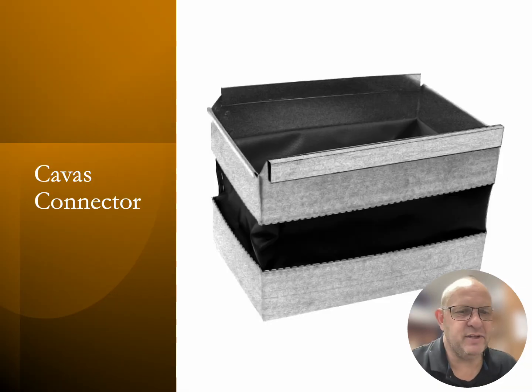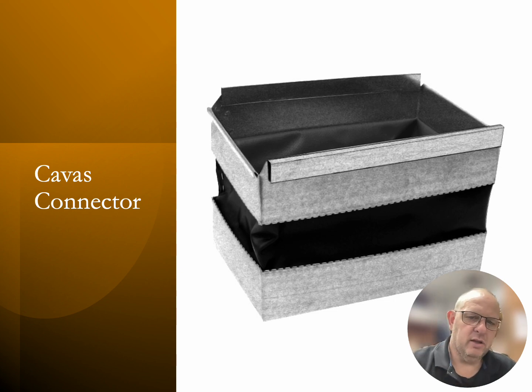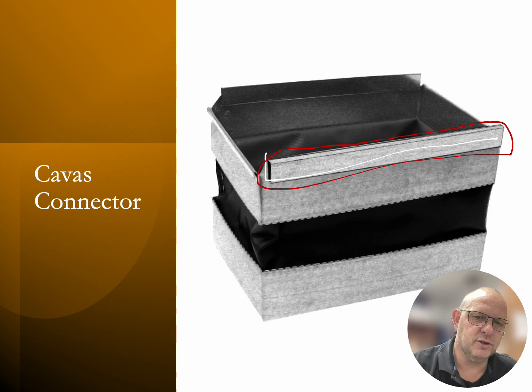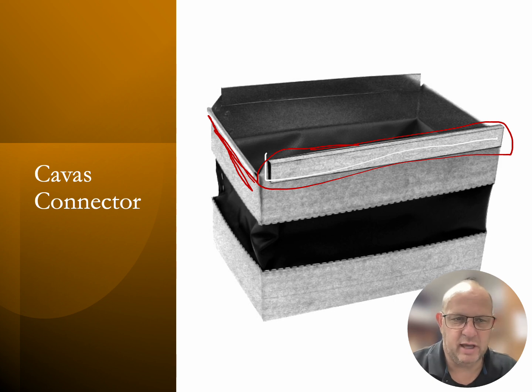Well, we talked about the canvas connector, as we can see on this particular picture. This is a canvas connector. Our S-lock is located in this area right here, and this is going to be hooked onto our square duct. Then we have our drive cleat that's going to go on this section right here for our canvas connector. The canvas connector is there to stop vibrations from transferring from the air handling unit through the ductwork and into the living environment of individuals out there.